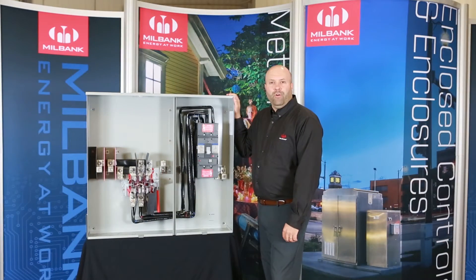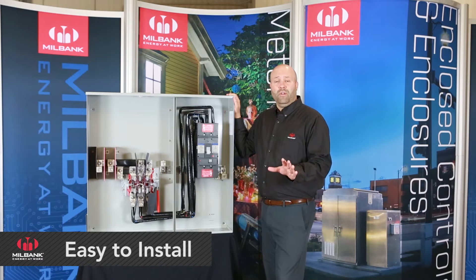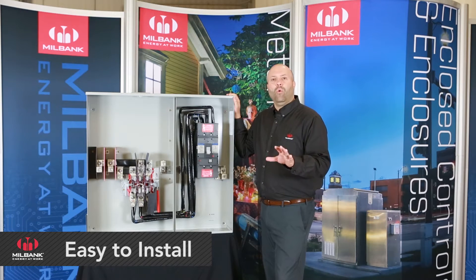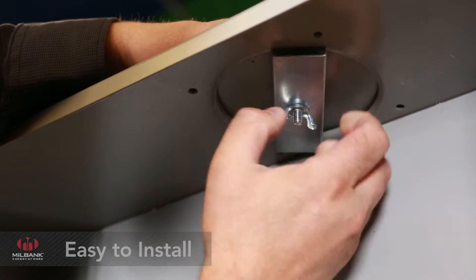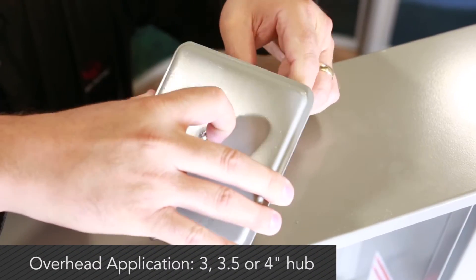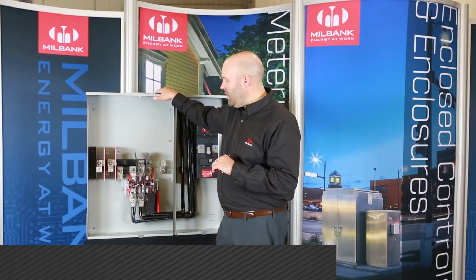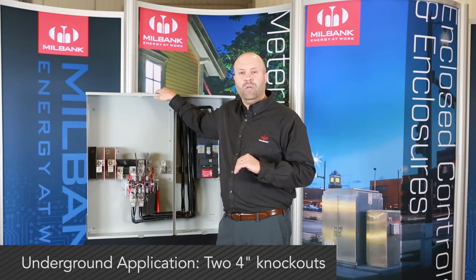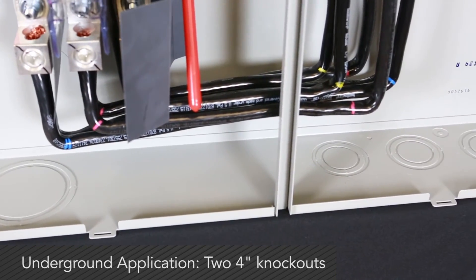The Milbank 400 amp meter main comes from the factory ready to be installed in either overhead or underground applications. It comes equipped with a closing plate, which can be easily removed and replaced with a three, three-and-a-half, or four inch hub for overhead applications. For underground applications, it comes with two four inch knockouts included in the unit.